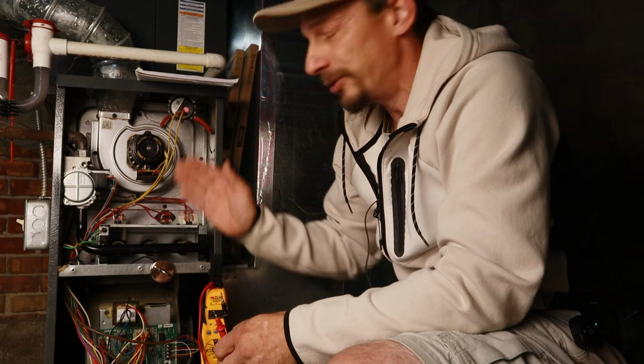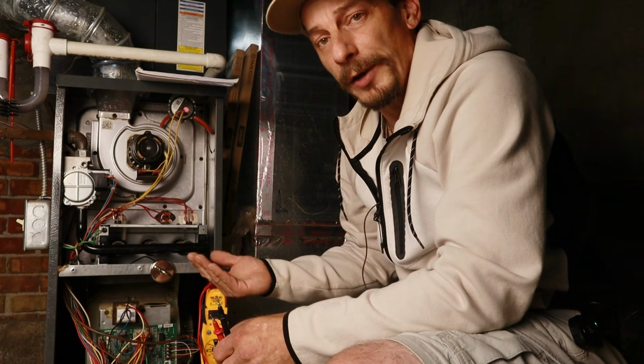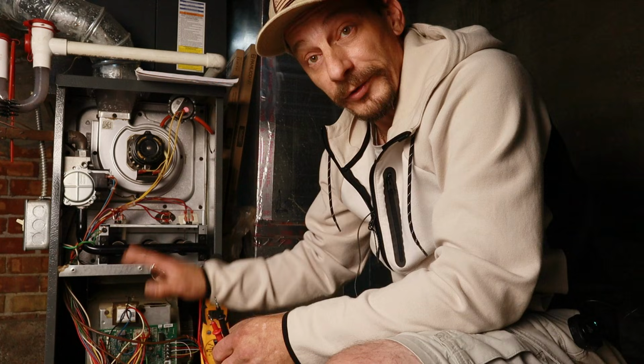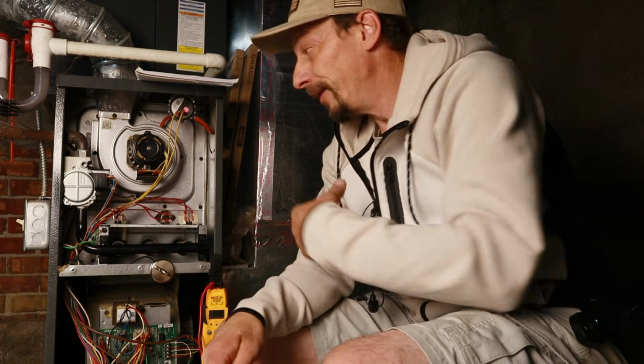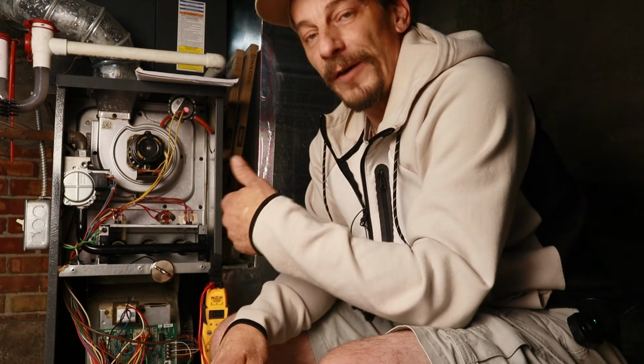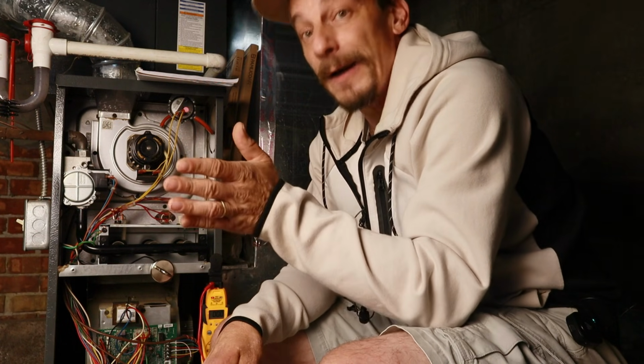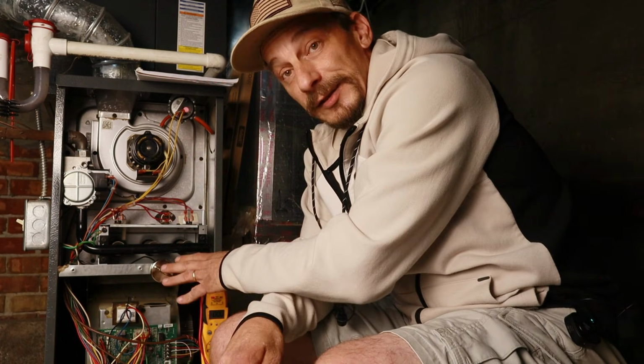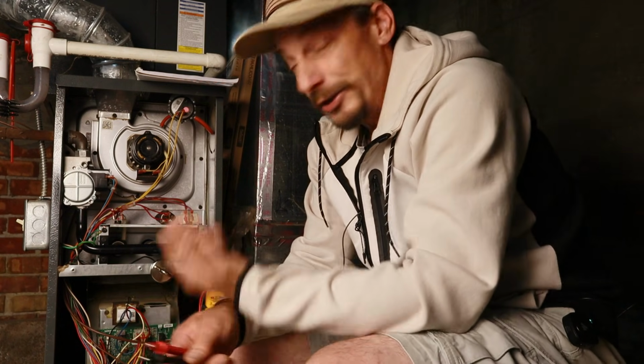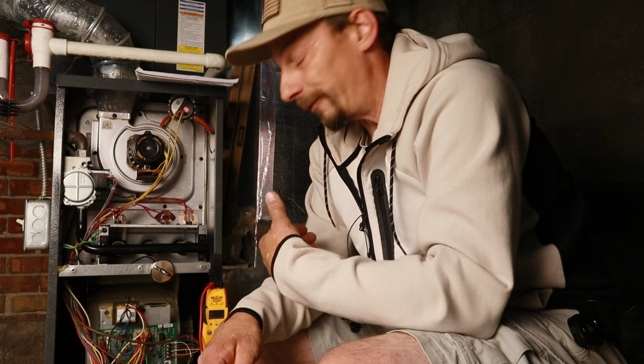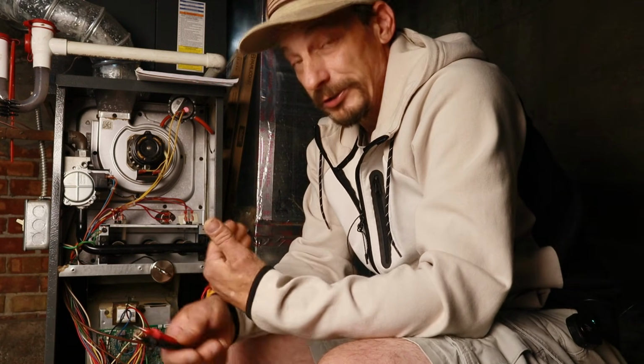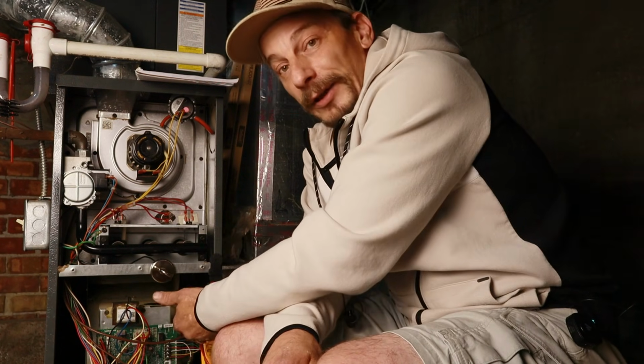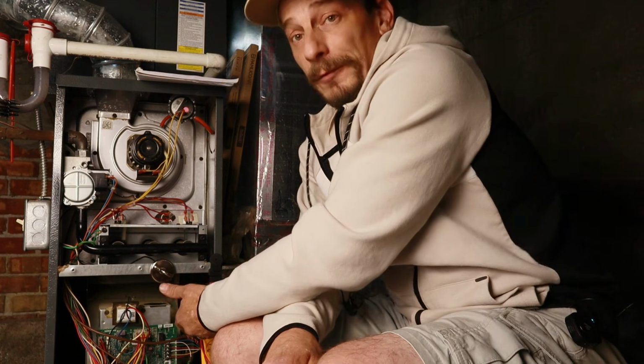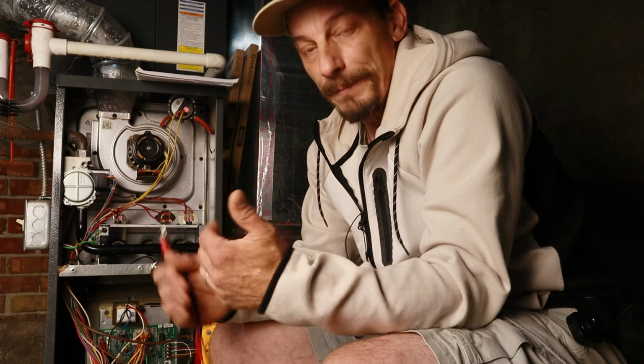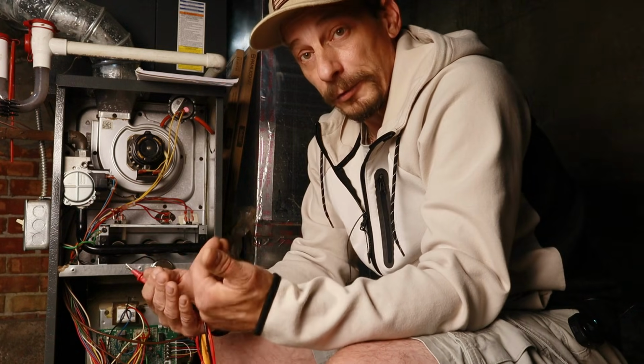It's not so much the functions that need to happen for the unit to run and work, it's all the safeties that are worked into it. On top of that, you have optional features, humidifiers, UV lights, makeup air, all kinds of other things that are worked into these circuits as well. So basically what it comes down to is safety and sales, and then you have advances in technology. So instead of a regular split capacitor motor with just 2 or 3 wires coming to it, you have an ECM motor that has several more wires. So it does pile up, and using schematics really helps you work through it once you know how to read them.